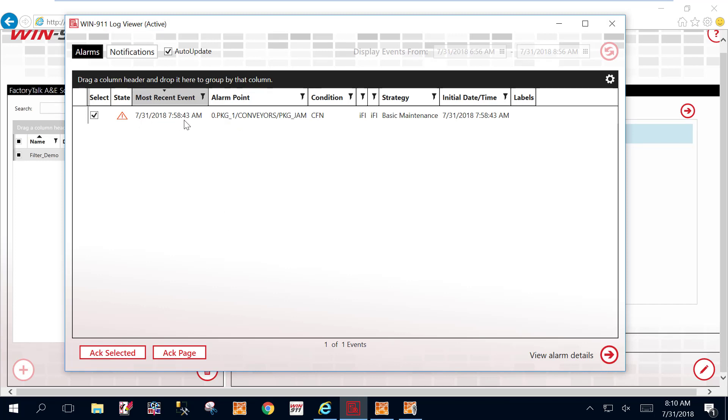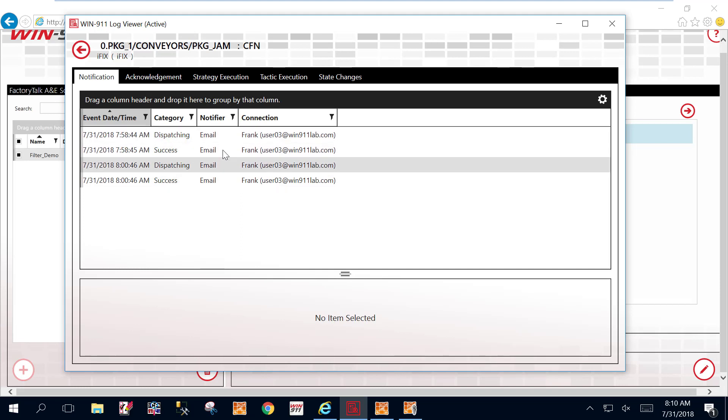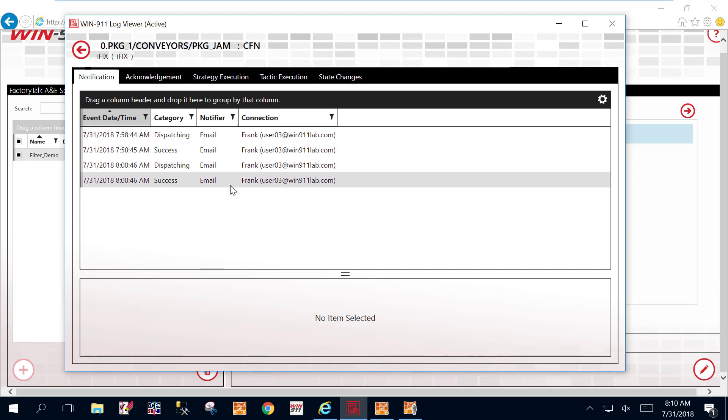And you can use this do not notify strategy in your Win911 log viewer. So this is a tool that we have for troubleshooting. And in here it shows the alarm that went off, what it was, the time, all that. And it also shows which strategy you went to. So say, for example, the strategy is going to do not notify. You thought it was supposed to go to our operator strategy. That's an indicator that maybe you typed something wrong in your configuration. So that's our troubleshooting tool with the log viewer. You can also click on it and see some of your alarms and details of who it went to and things like that. So this one went to Frank, is dispatched, is successful. This is helpful for doing call-outs, determining who your alarms went to and if they went to the right person.